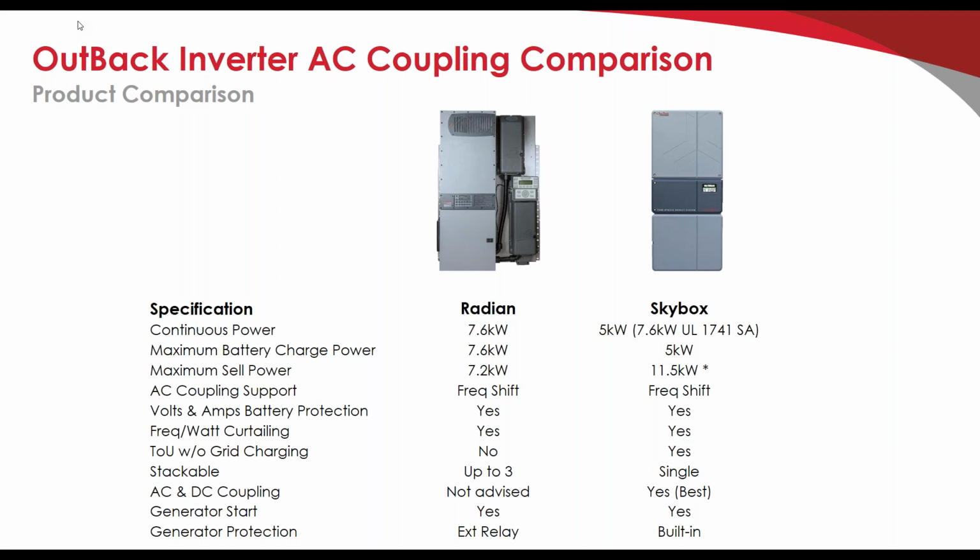Both inverters support AC coupling via frequency shift. Both provide volt and amps battery protection. Both do frequency watt curtailing.